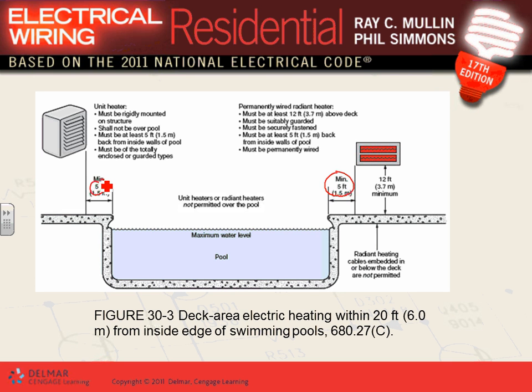It must be at least 12 foot high. So they put this particular one 12 foot high, suitably guarded, secured, and permanently wired. It's not plugged in. If you have a radiant heater, there are regulations on how to install it. Don't put it closer than 5 feet. Elevate it, because people are still running around here, right? When they're swimming, they're running barefoot in this area. If you put this one at 7 foot, people can stand there and catch it and could get a shock. So look at that. They elevate it and move it away from the swimming pool.